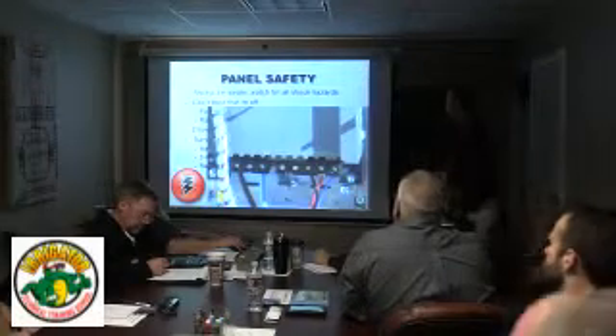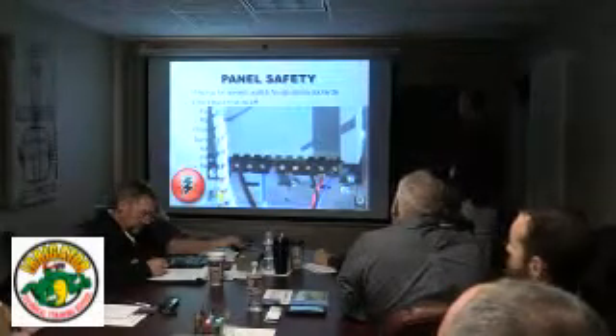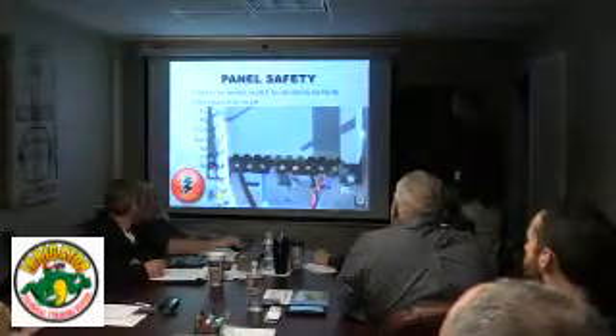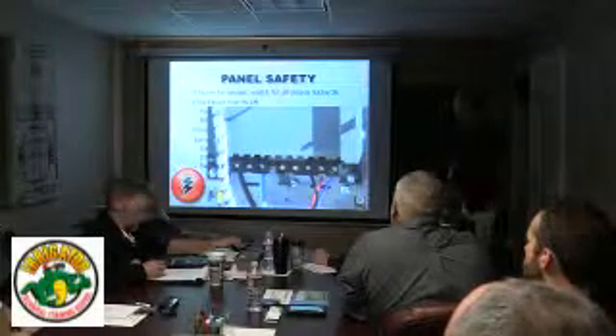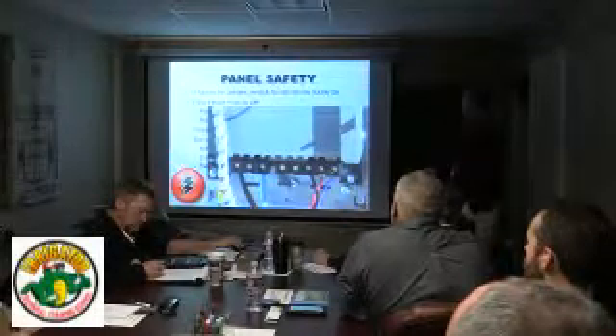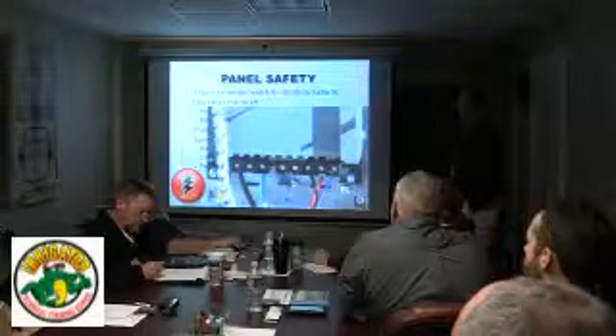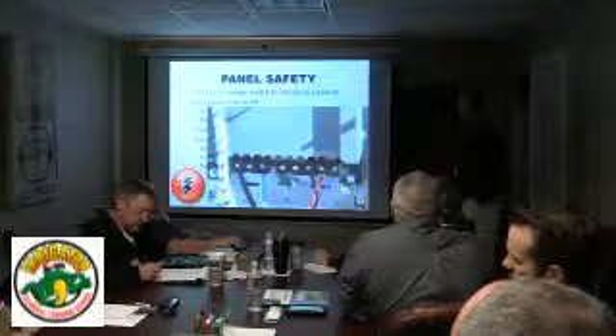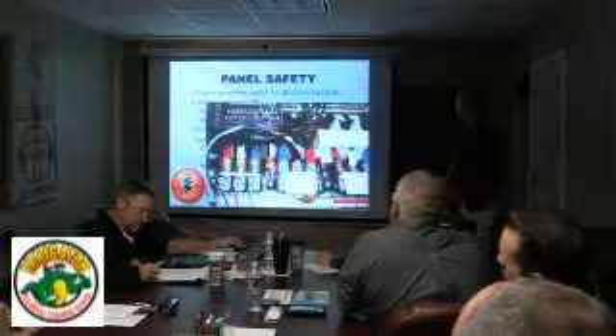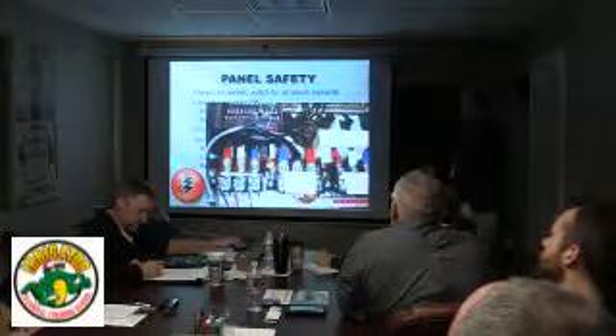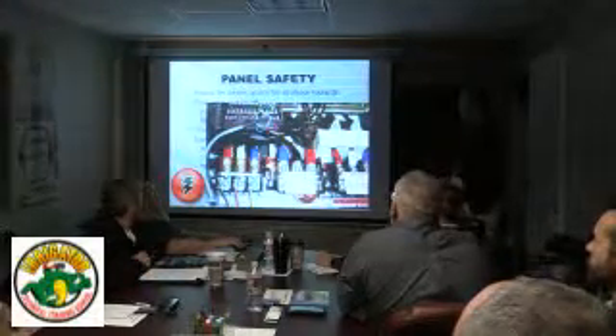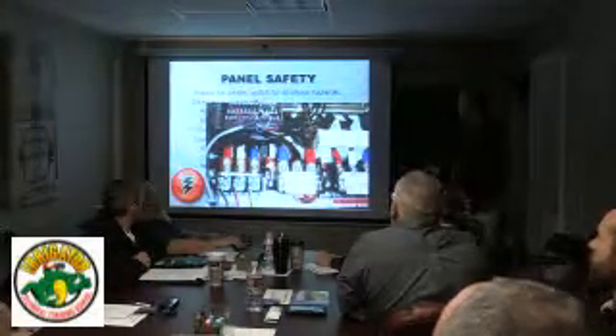Here's one. This is an ABB drive. This is your DC bus right here. So if you have to pull the power wires or the motor leads out, you are kind of close. This one is not so easy to touch. But there's another drive. Here's a Mitsubishi. You can see it's a little more open. These red, black, and blue here, these are your DC bus voltage, the red and black. If you do have to remove motor leads, here you could touch that.